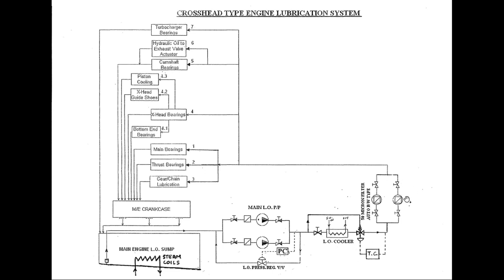The lube oil fine filter is a 30 to 50 micron auto backwash type. A duplicate filter is provided so the filter can be cleaned during engine running without having to stop the engine. Thereafter, oil goes to various places as shown in the figure, including main bearings, thrust bearing, and gear and chain lubrication.